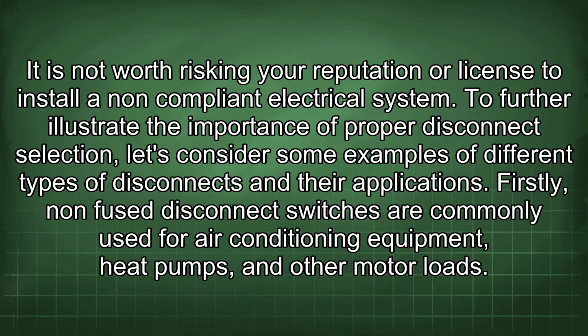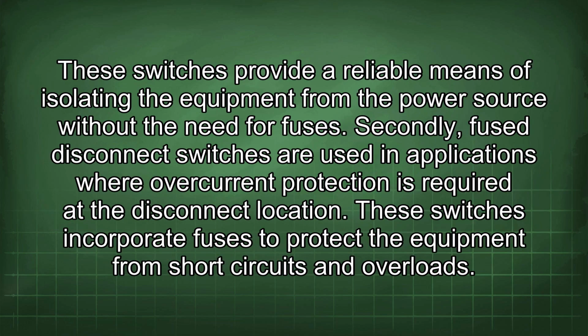To further illustrate the importance of proper disconnect selection, let's consider some examples of different types of disconnects and their applications. Firstly, non-fused disconnect switches are commonly used for air conditioning equipment, heat pumps, and other motor loads. These switches provide a reliable means of isolating the equipment from the power source without the need for fuses. Secondly, fused disconnect switches are used in applications where overcurrent protection is required at the disconnect location. These switches incorporate fuses to protect the equipment from short circuits and overloads.